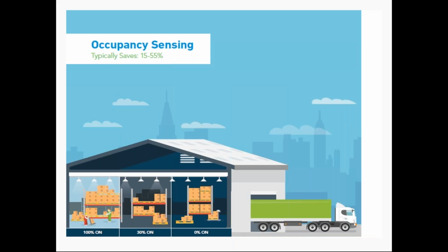I've heard from many customers, 'I can't use sensors because I'm a 24/7 facility,' or 'I can't have my lights turn off.' The great news with occupancy sensing today is that you can choose any percentage you want to dim the lights to when the space is unoccupied. If you need 20% light for safety, no problem. If you want to maintain 50% of normal light when nobody's in the space, that's easy to do as well. Programming the sensor is simple.